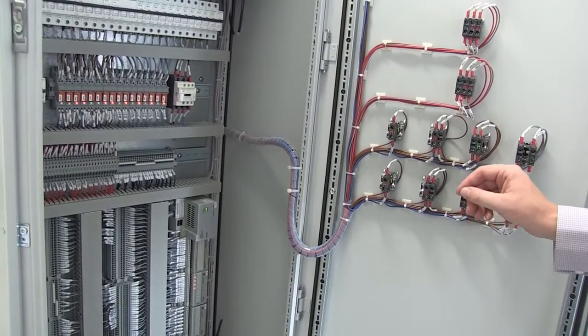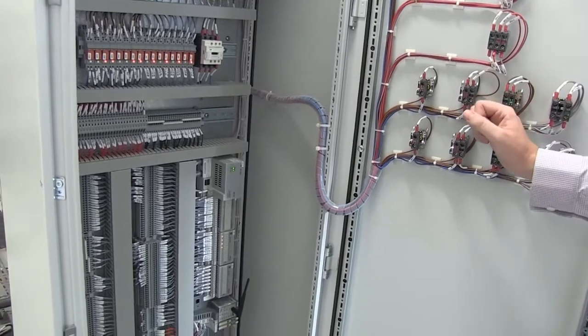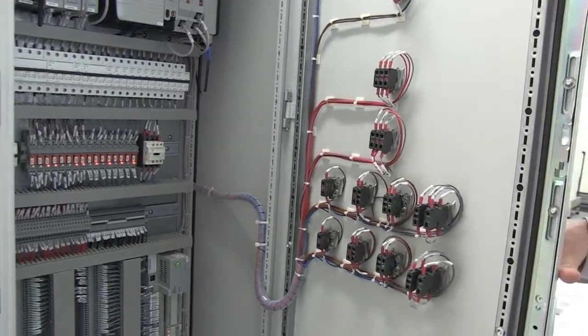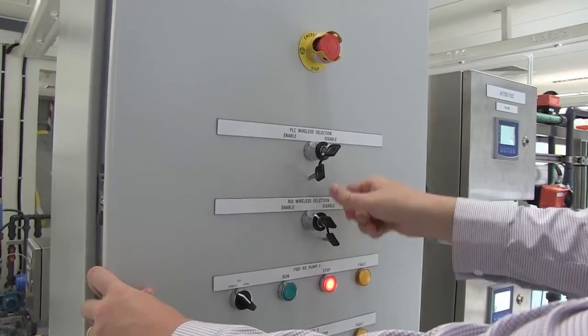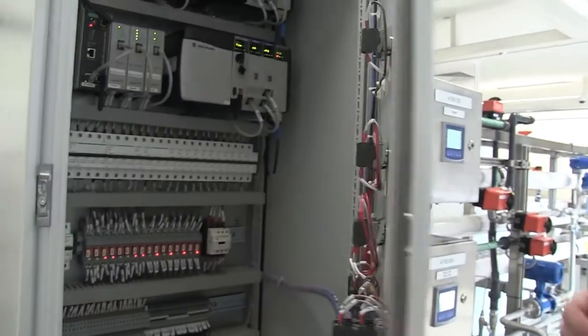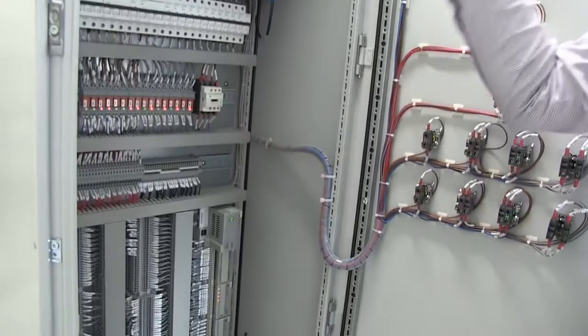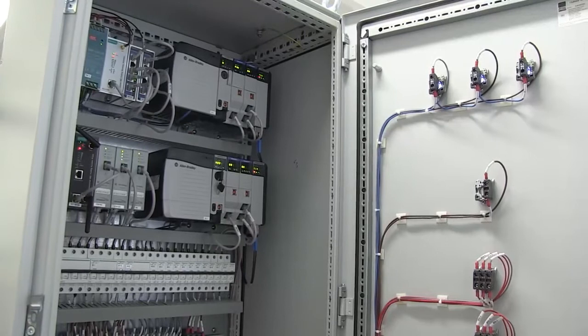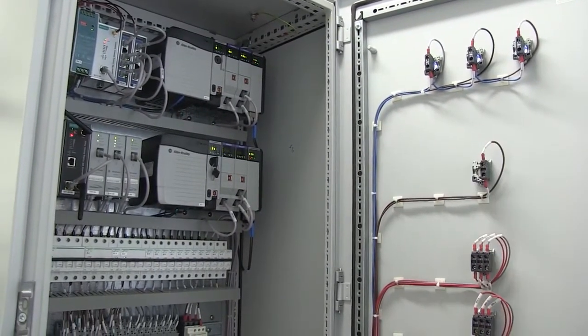In both the Level 1 and the Level 0 network, we mainly use wired network connectivity. We are always able to switch into a wireless connectivity mode by flipping a switch provided on the casing. Enabling wireless communication here will automatically disable the wired connections. In this case we would have switched both the Level 0 network and the Level 1 network of this PLC to wireless communication, so the PLCs communicate with the remote I/O and with other PLCs over a wireless link.